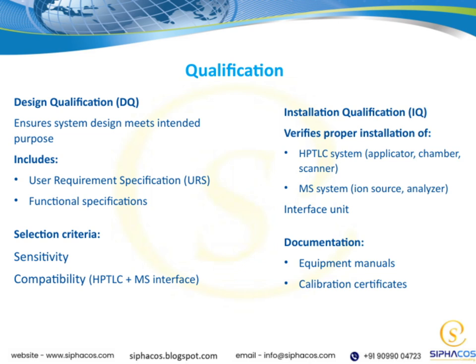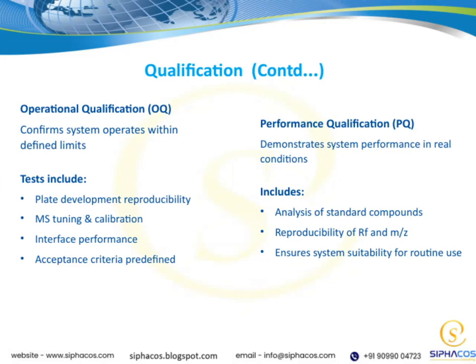Now, let's talk about performance qualification, or PQ. This is where we demonstrate that the system performs reliably under real-world conditions. Essentially, we're testing the system as it would be used day to day. Key components include analyzing standard compounds to verify the system can accurately identify and quantify them. We also look at the reproducibility of Rf values and m/z ratios, which helps ensure consistent results across different runs. This process is crucial because it confirms the system's suitability for routine analytical work, giving us confidence in the data we generate.